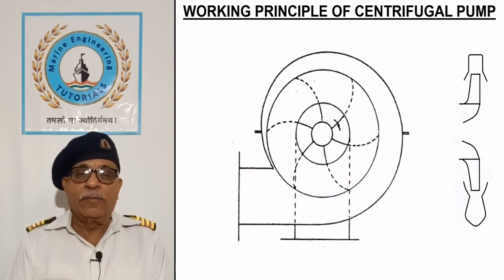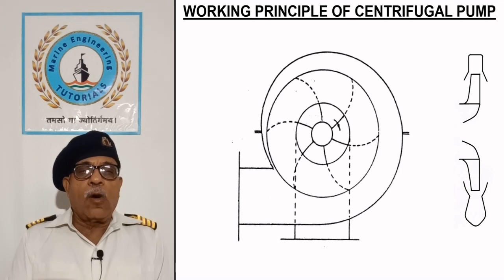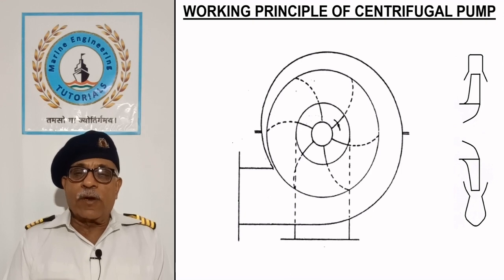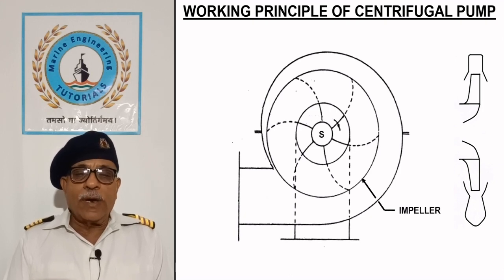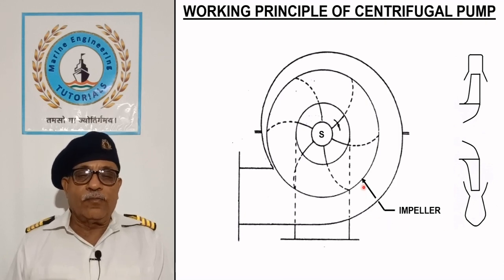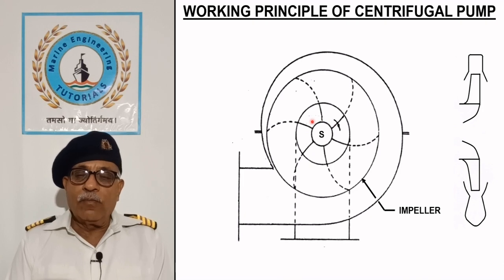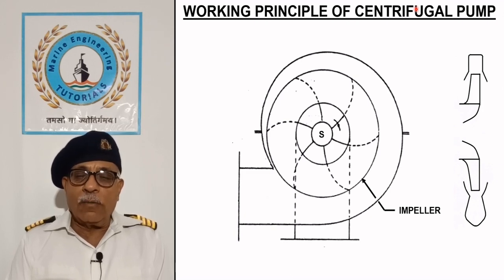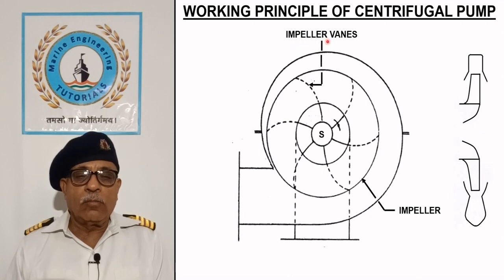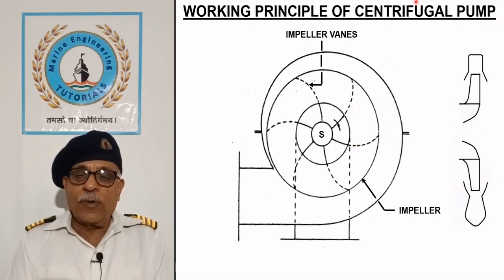Working principle of centrifugal pump: this sketch explains the working principle. The pump casing should be filled up by the liquid before the pumping action can take place. The pump consists of an impeller attached to a shaft driven by a prime mover, which can be an electric motor, a hydraulic motor, a diesel engine or a steam turbine. The impeller has a number of vanes which displace the liquid, dragging it between them, thereby imparting kinetic energy to the liquid.